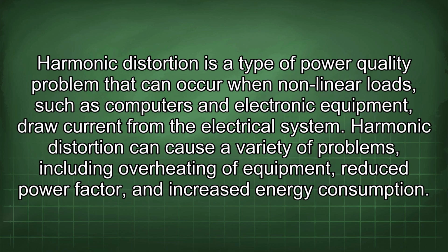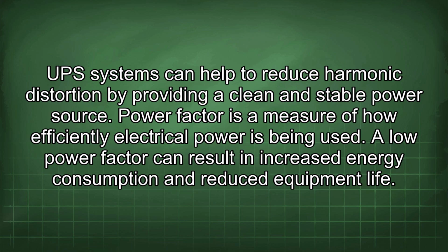Harmonic distortion is a type of power quality problem that can occur when nonlinear loads, such as computers and electronic equipment, draw current from the electrical system. Harmonic distortion can cause a variety of problems, including overheating of equipment, reduced power factor, and increased energy consumption. UPS systems can help to reduce harmonic distortion by providing a clean and stable power source.